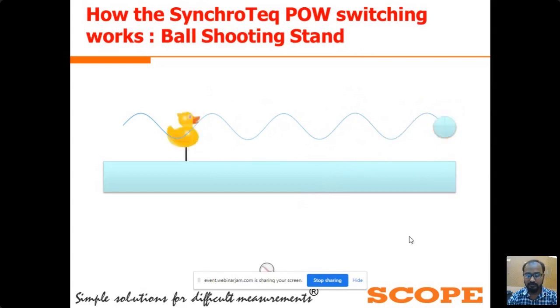Here you can see we have the reference of this sinusoidal waveform. The CSD knows when the target point is coming, and it also knows the speed of this ball, that is the breaker operating time. The only thing the CSD has to calculate is the moment to release this ball, that is the moment to execute the command to the circuit breaker. By calculating this particular moment, we can achieve this target point. Basically this is the principle of operation of the control switching device. The control switching device pre-calculates the moment to execute the command to the circuit breaker, so that we can target a specific electrical moment to operate the circuit breaker.